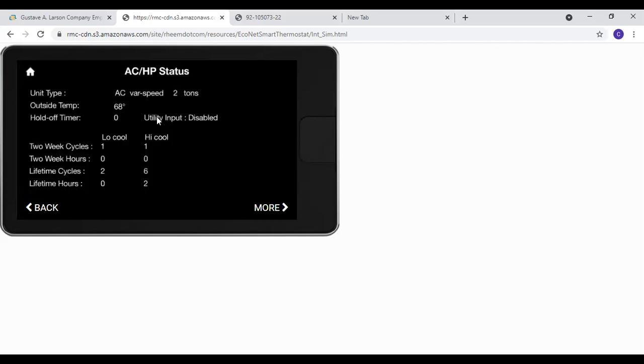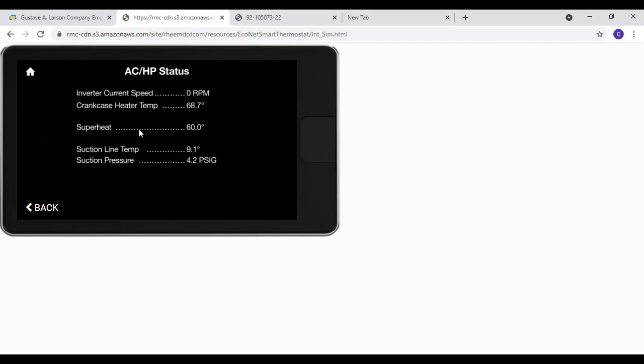Go back over here. If we go to the AC heat pump here, it kind of walks you through what you have. If you go to the additional screen, it will tell you exactly what your inverter current speed is. So if I think it was a 5-ton, it should be at 4,100 RPMs. So if you're in test mode and this is at 4,100 RPMs or close to it, then you know you've reached appropriate speed.